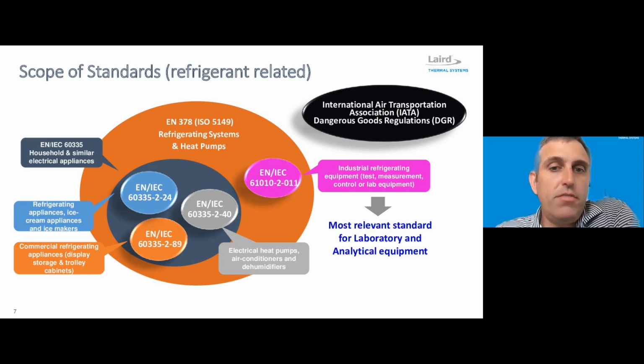All of these norms have their own specific standards, but then they also rely upon EN 378, which is what I show here in the bigger orange area that kind of has a fallback of use of refrigerants in general. And so then I show outside of this, in this black area, there's another very specific standard that comes from the IATA, which is the International Air Transportation Association. And so they have, for obvious reasons, some requirements in terms of how much of this refrigerant can be used, especially if it's a flammable refrigerant. So they put limitations upon how much can go into a single system that they're going to be transporting around the world. And we'll talk a little bit more about that.